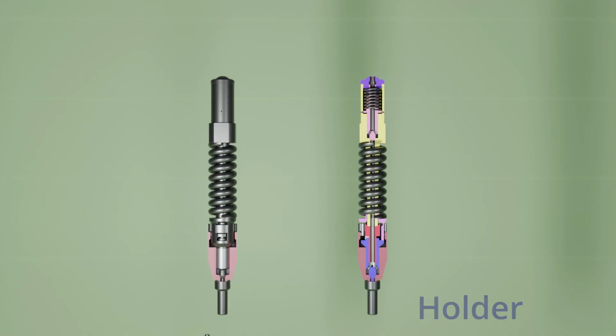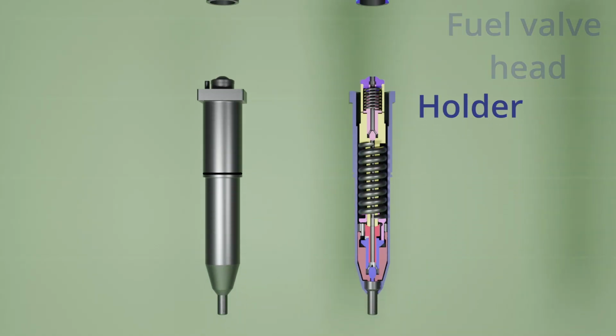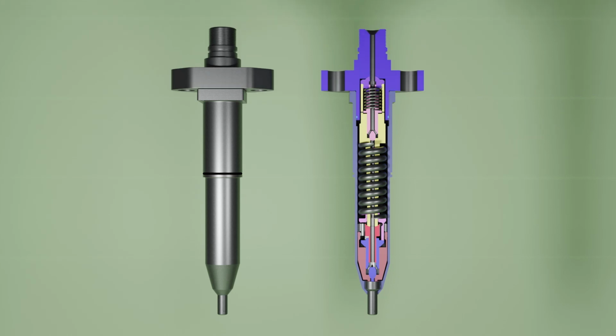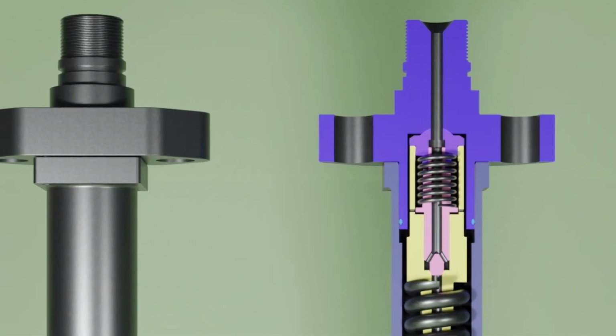Finalizing the assembly, we have the holder, fuel valve head, and securing screws. Notice the contact surface between the thrust piece and fuel valve head. These surfaces should be checked for imperfections and same can be lapped using their respective tools.